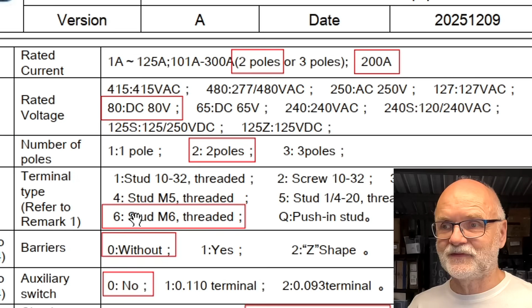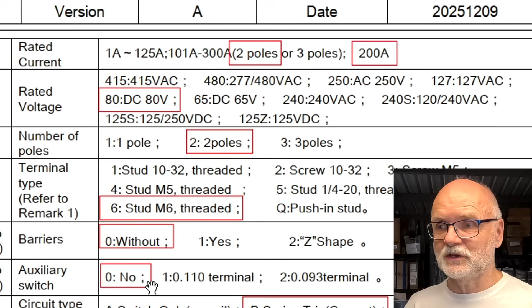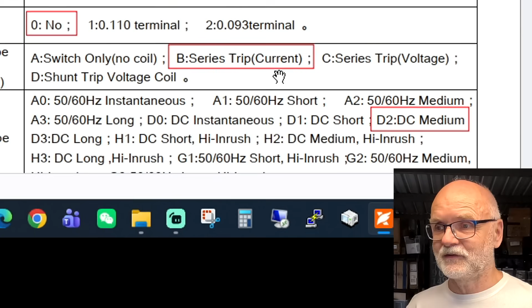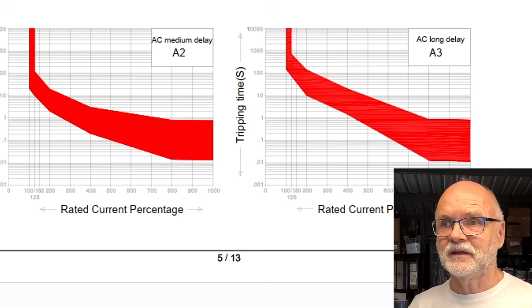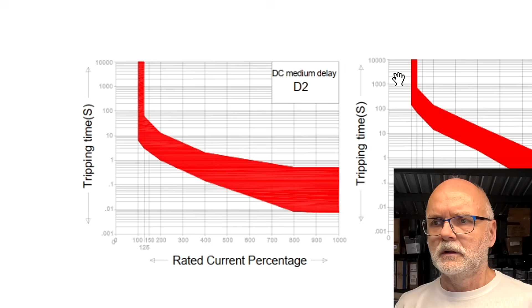So here we've got more information. It's a 2-pole, 200 amp, 80 volt DC rated, 2 poles, M6 studs, without barriers in between. It has no auxiliary switch, B series trip current. DC medium delay type is D2. What we have seen on the label means DC medium. And we also have some trip curves here. Very nice. Okay, so we have to look at DC medium delay. That's what we have, and this is the trip curve.